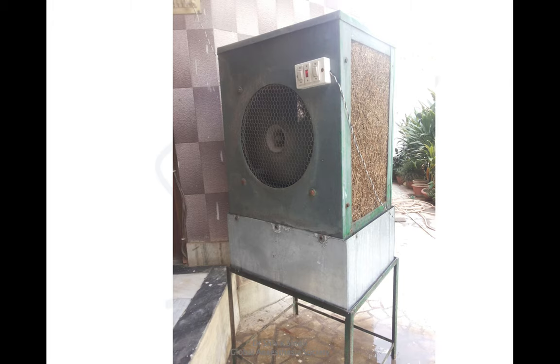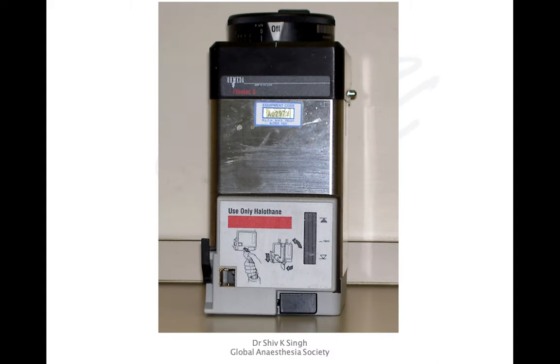Same thing is this is the air cooler, and in the air cooler the water is getting evaporated. As the water evaporates, it drops the temperature of the air surrounding it. So these principles are used in vaporizers. I'm not saying that the evaporation will improve the accuracy, but I was saying that it will reduce the accuracy because as the evaporation reduces, the vapor pressure will actually drop within the chambers of the vaporizers.